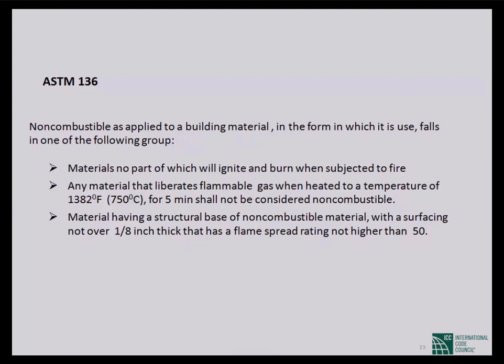You can ask why it is 750 degrees. Actually, in our building, the temperature rise whenever there is a fire is within this limit. Before 1950, this definition was different. This temperature was 1250, but now the standard changed its value. Now it is 750 degrees centigrade.